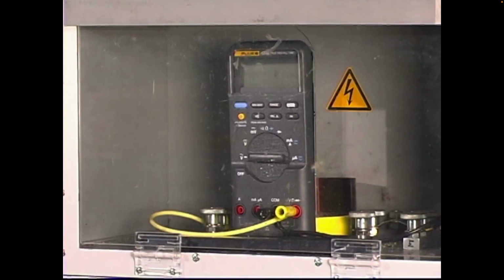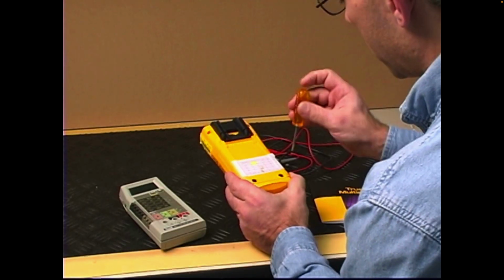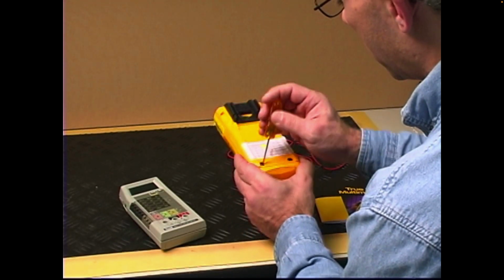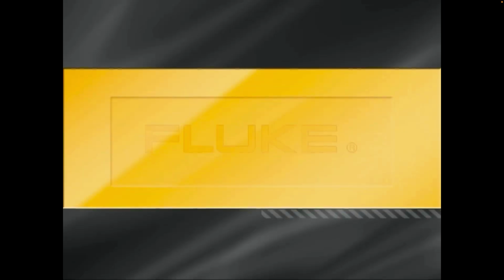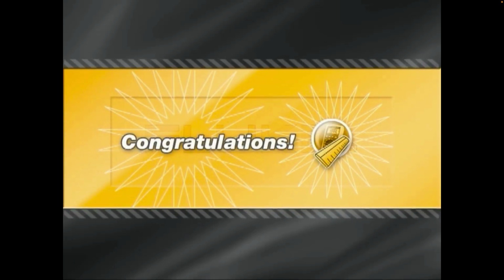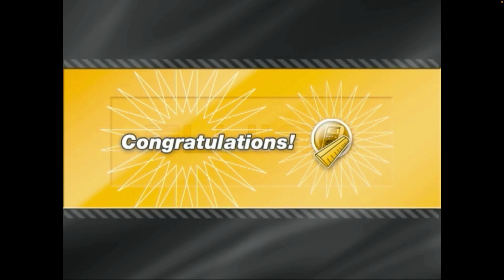Finally, if you've ever had a blown fuse or mishap with your test instrument, make sure you get it checked out and properly calibrated before using it in a high-energy environment. If your test instrument passes these tests, congratulations. You are successfully managing some of the risks inherent in measuring electrical equipment.